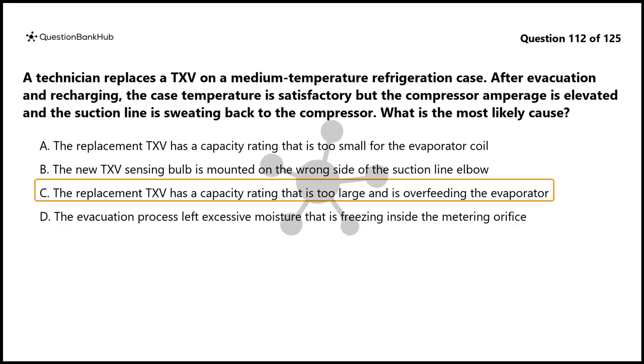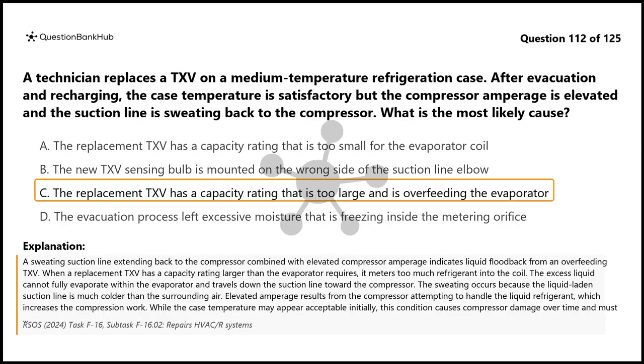The correct answer is C. A sweating suction line extending back to the compressor combined with elevated compressor amperage indicates liquid flood back from an overfeeding TXV. When a replacement TXV has a capacity rating larger than the evaporator requires, it meters too much refrigerant into the coil. The excess liquid cannot fully evaporate within the evaporator and travels down the suction line toward the compressor. The sweating occurs because the liquid-laden suction line is much colder than the surrounding air. Elevated amperage results from the compressor attempting to handle the liquid refrigerant, which increases the compression work. While the case temperature may appear acceptable initially, this condition causes compressor damage over time and must be corrected by installing a properly sized valve.